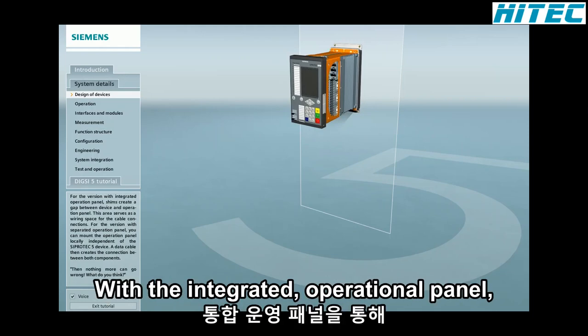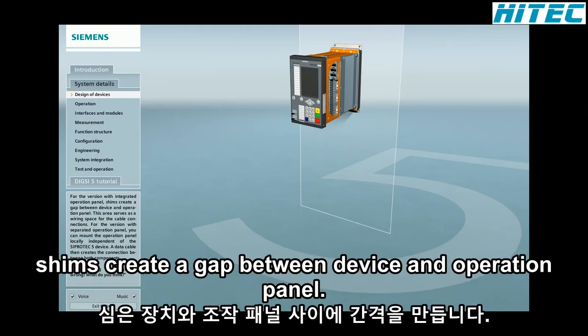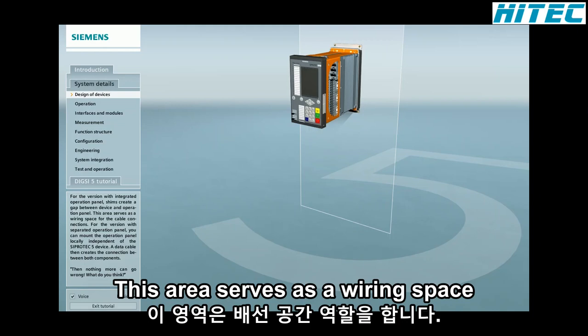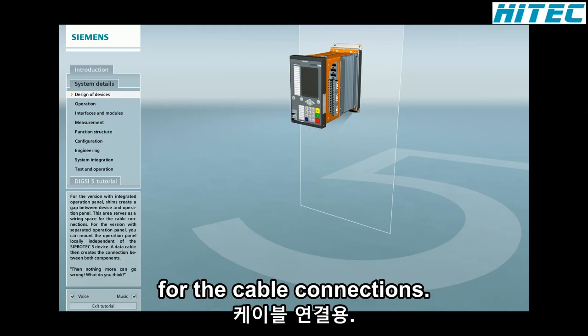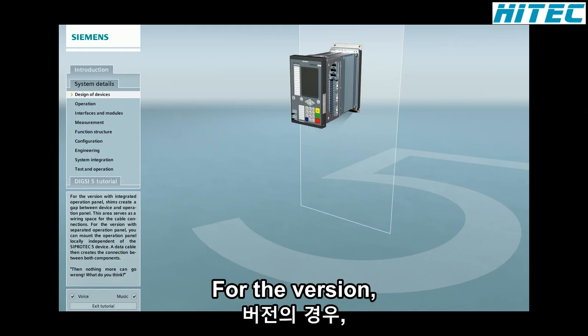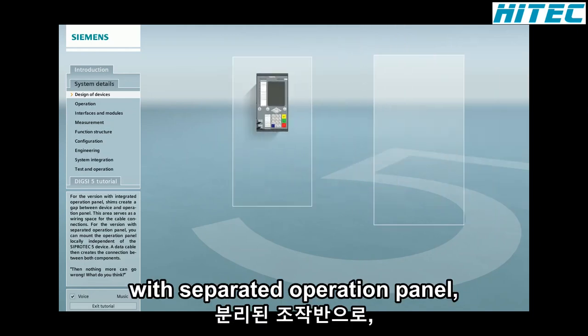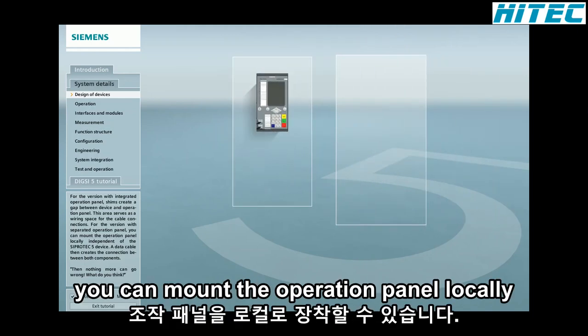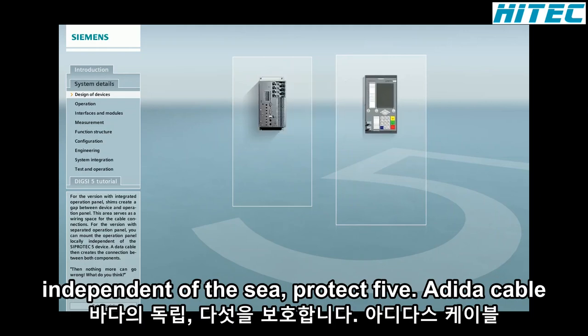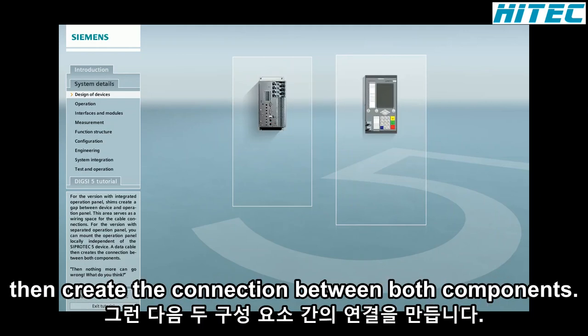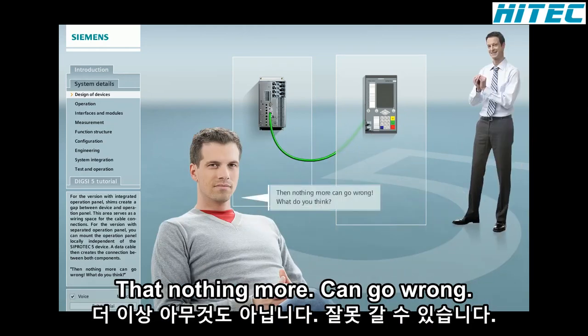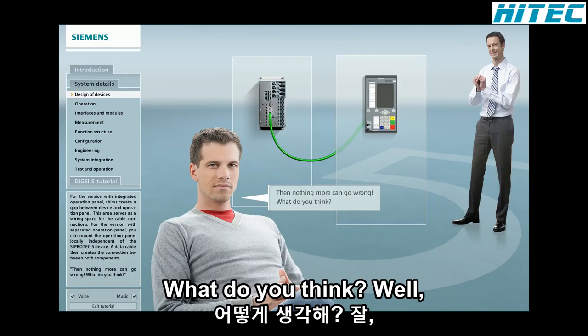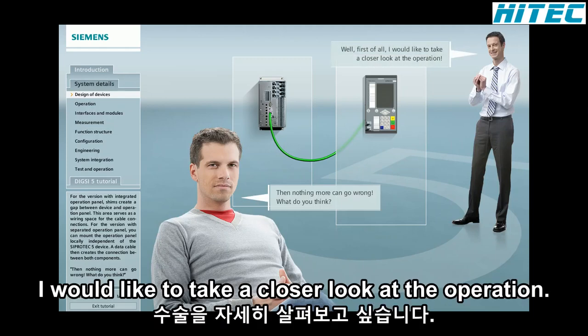For the version with the integrated operational panel, shims create a gap between device and operation panel. This area serves as a wiring space for the cable connections. For the version with separated operation panel, you can mount the operation panel locally independent of the SIPROTEC 5 device. A data cable then creates the connection between both components. Then nothing more can go wrong. What do you think? Well, first of all, I would like to take a closer look at the operation.